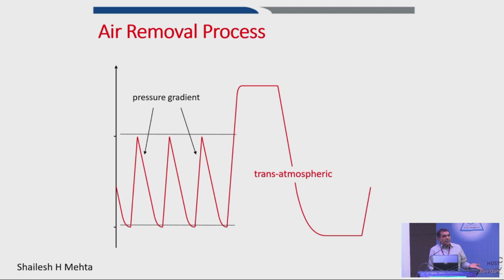The dilutions, the main thing: at home also you give 10 whistles, 5 whistles, 6 whistles basically to remove air. The more air you remove, because air is heavier than steam, that is a problem in the gravitational process. So the penetration of steam becomes a bit difficult. So the more air you remove, the deeper the penetration you get.